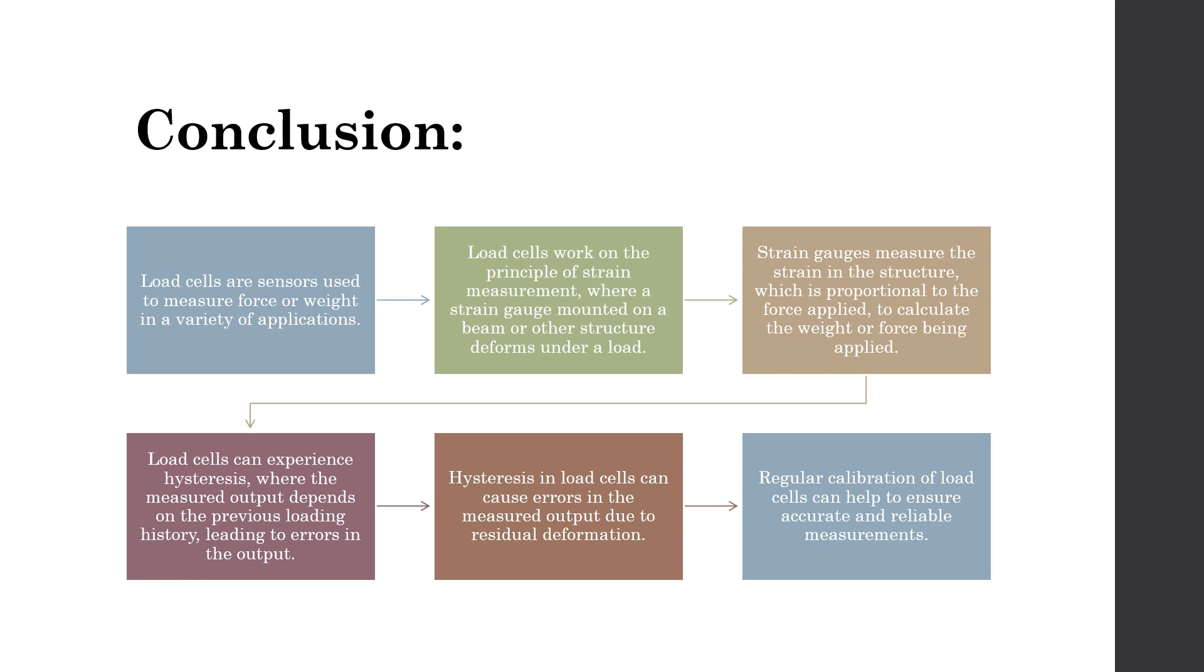Load cells can also experience hysteresis, which is the phenomenon in which the current output depends not only on the current input but also on the history of the loading. Hysteresis in load cells can cause errors in the measured output due to residual deformation. So regular calibration of load cells is required to maintain the accuracy and reliability of the load cell.